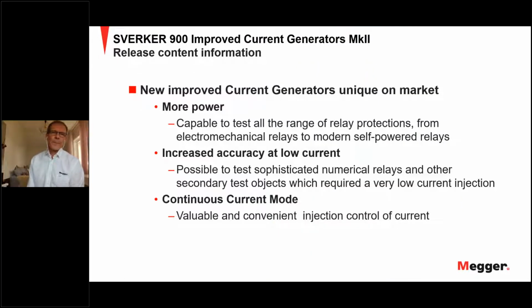So last year we improved the current generators on Sverker 900, and that improvement is the Sverker 900 Mark II. With that improvement, we get more power. So it's capable of testing the whole range of relay protection, from electromechanical relays to modern relays. Especially, we have taken care in the development to be able to test all the self-powered relays and the problems and difficulties they have in testing.